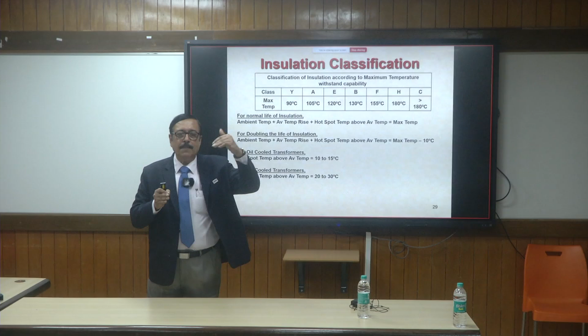So insulation will come according to certain classes depending on the maximum temperature withstand capability, as in the table. The maximum temperature withstand capability of the transformer is going to be decided by the ambient, the average temperature rise of the transformer, and the hotspot temperature, because I said average, there will be some point which has the highest temperature, and that highest temperature must be at least 10 degrees centigrade lower than your maximum temperature for the insulation to survive. Otherwise, the insulation does not survive.